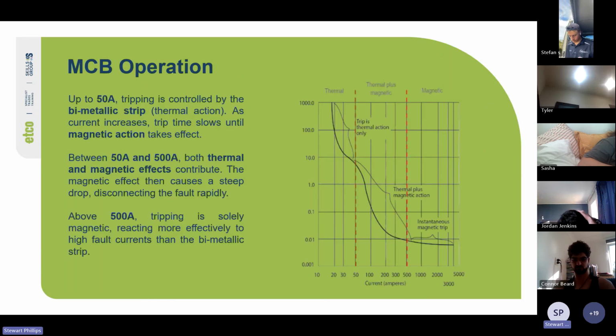Here there's an MCB operation curve. Up to 50 amps, tripping is controlled by the bimetallic strip, so it's a thermal action. As current increases, trip time shortens until magnetic action takes effect. The way the bimetallic strip works is that because they're two dissimilar metals, one wants to heat and expand more than the other one, so it bends more in one direction than the other, causing the trip mechanism to actuate. Between 50 and 500 amps, both thermal and magnetic effects contribute. The magnetic effect then causes a steep drop, disconnecting the fault rapidly. Above 500 amps, tripping is solely magnetic, reacting more effectively to high fault currents than the bimetallic strip.